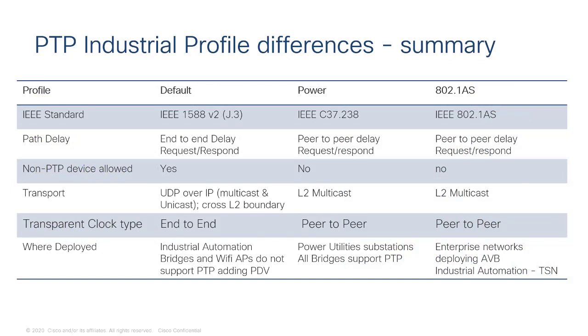There's no one way for PTP protocol to work. Different industries have determined they need PTP to operate slightly differently. There are 12 profiles that we know of, and the three we call industrial are the default, the power, and 802.1 AS — each with their own standard as defined by IEEE. There are some slight differences between them, but the big one that shows up in the messaging is the operation of the transparent clock: there's an end-to-end transparent clock type and a peer-to-peer transparent clock type, and different profiles use different transparent clock types.